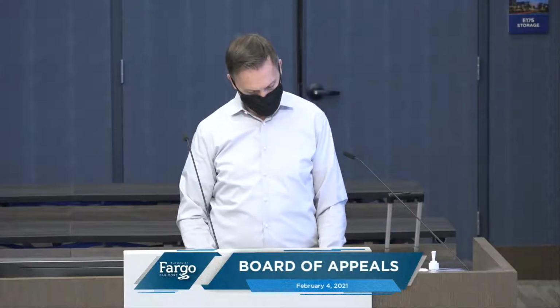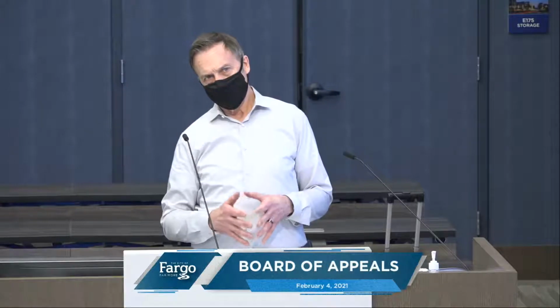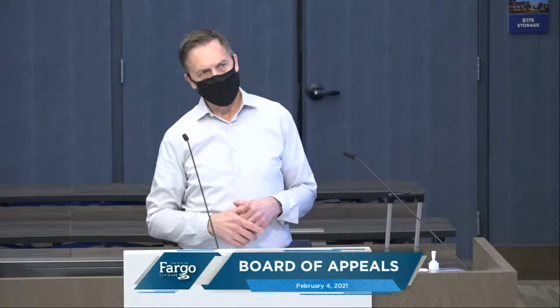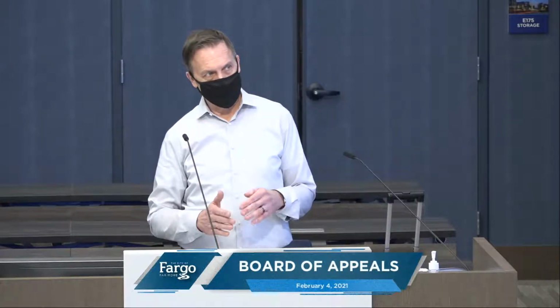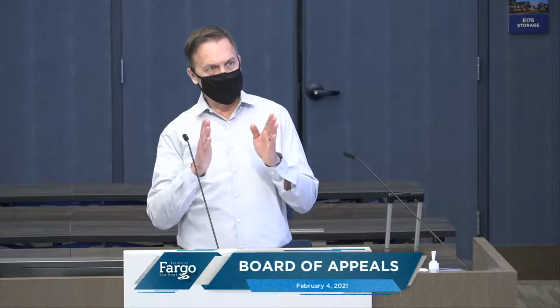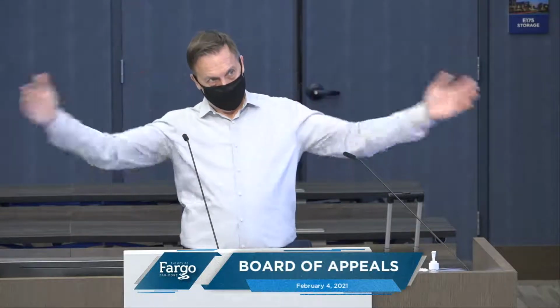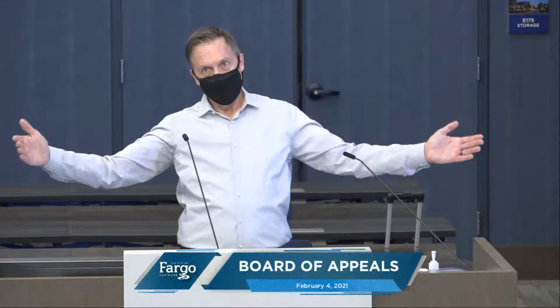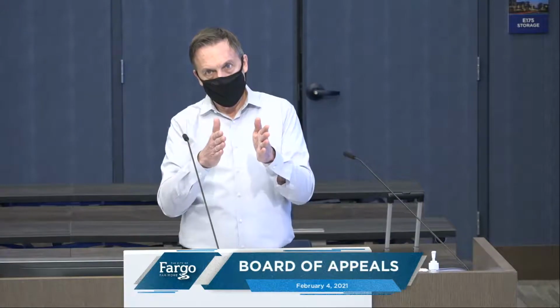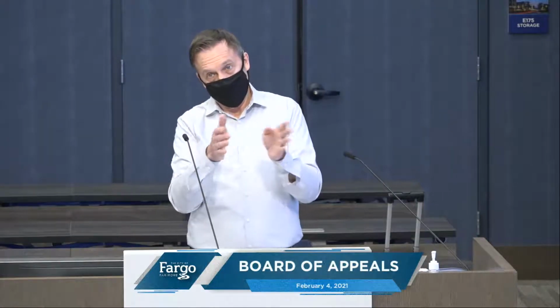And so fire barriers have a little bit different requirement for vertical continuity than fire walls. Fire walls need to go to pretty much the exterior skin, and then they have requirements even outside that skin. Fire barriers can just go to the outside wall. If it's a 1 hour wall, it should go to the skin.